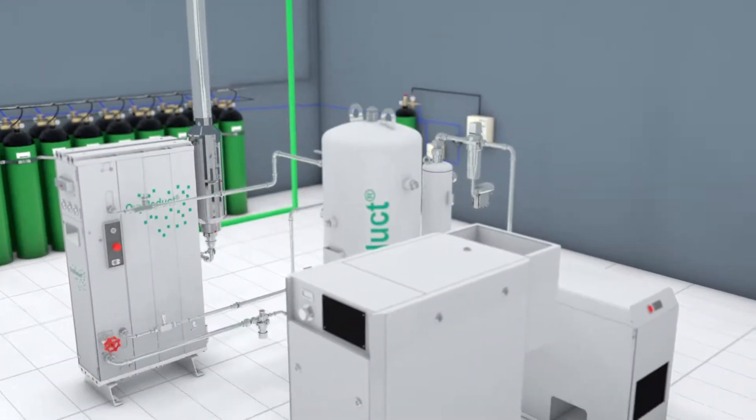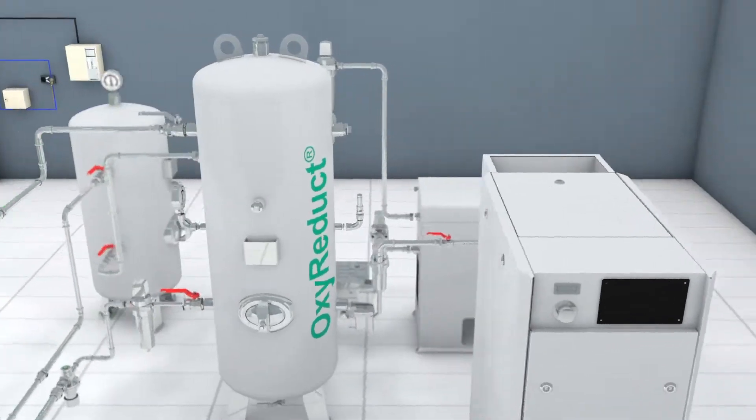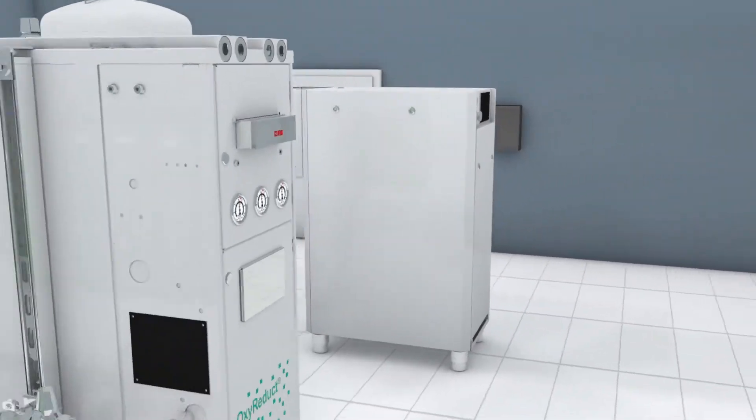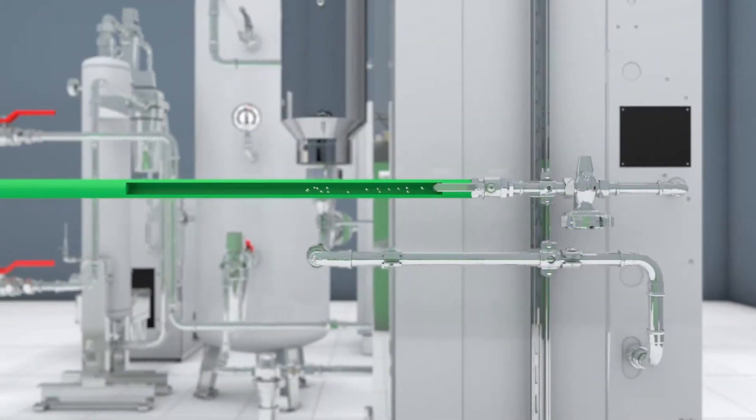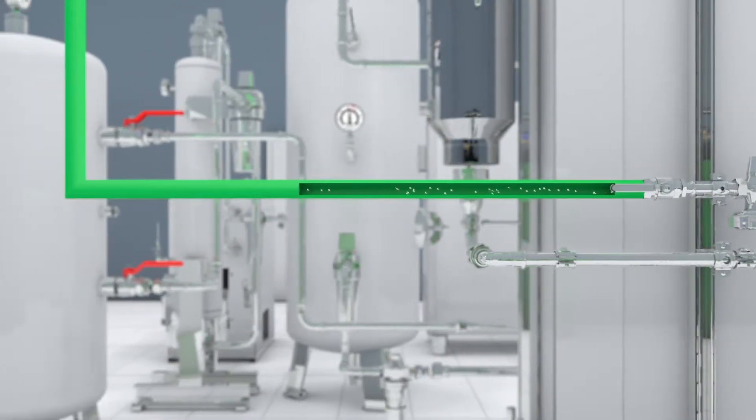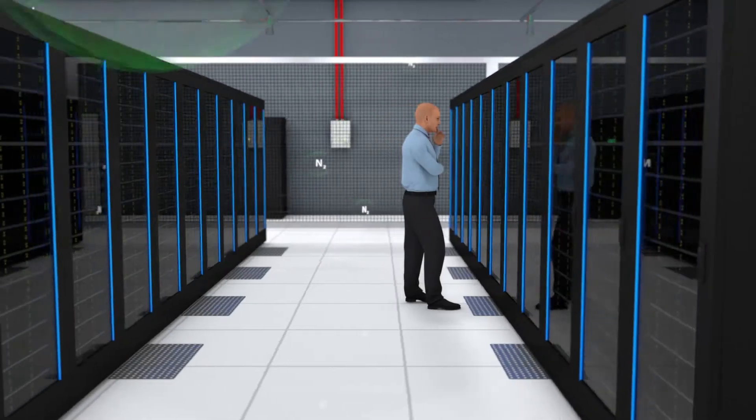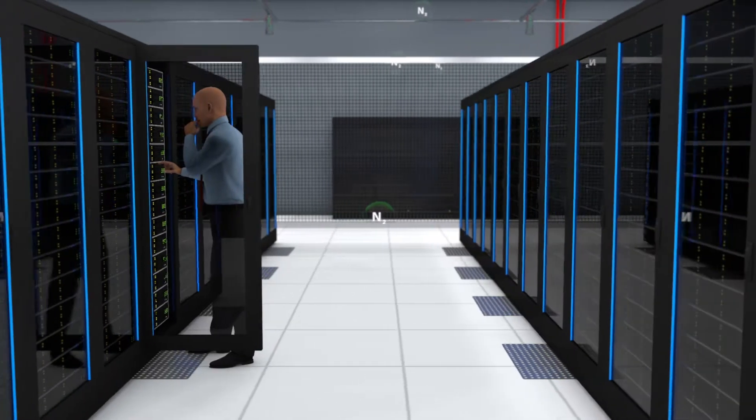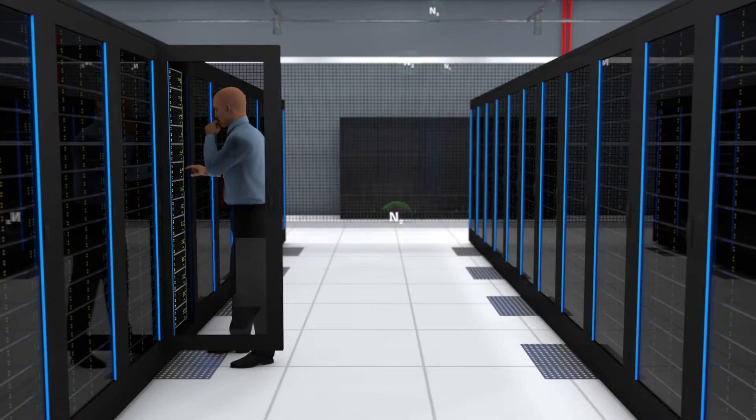A nitrogen generator of the OxyReduct system keeps the oxygen level at a constant 17.0% by volume for as long as necessary. There is still enough oxygen to enter the protected area and the operator is able to locate the cause of the fire and fix the problem.